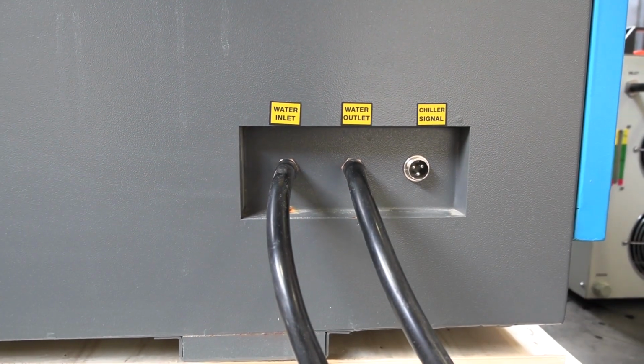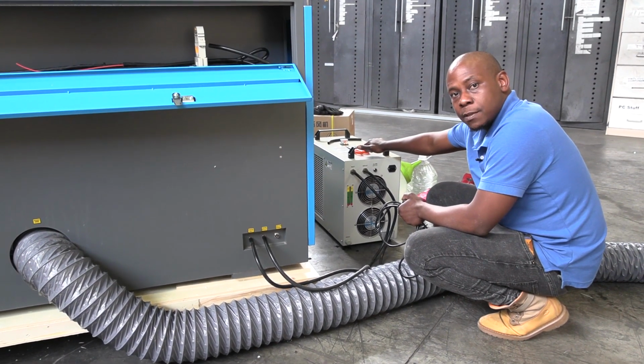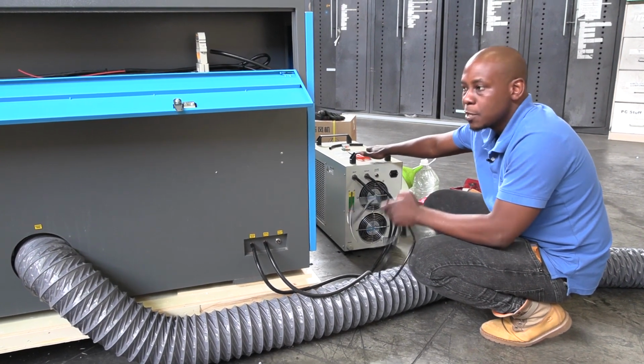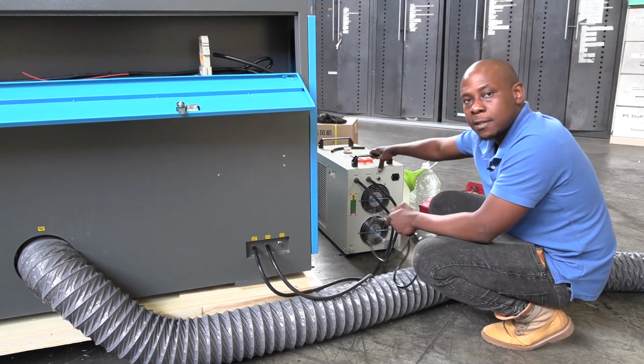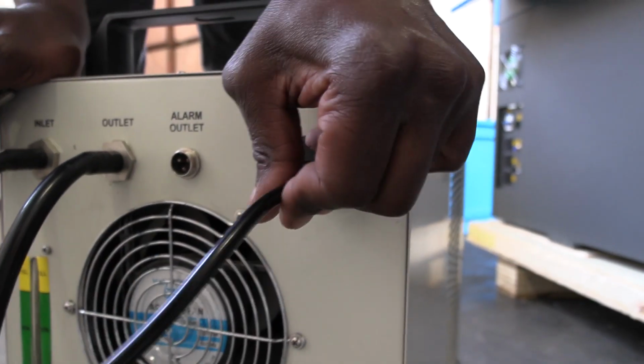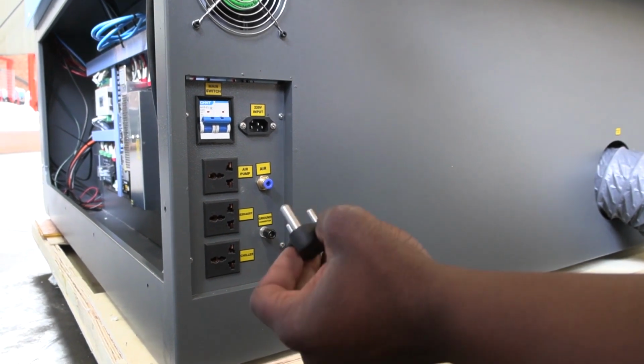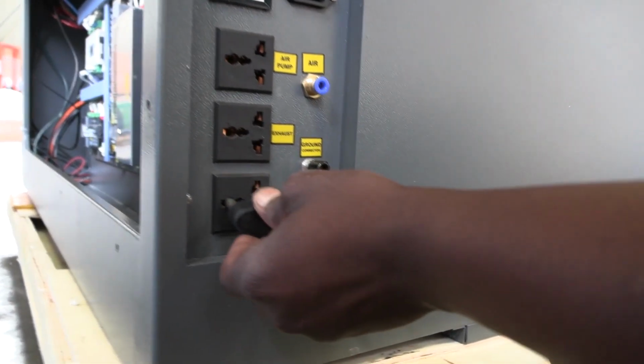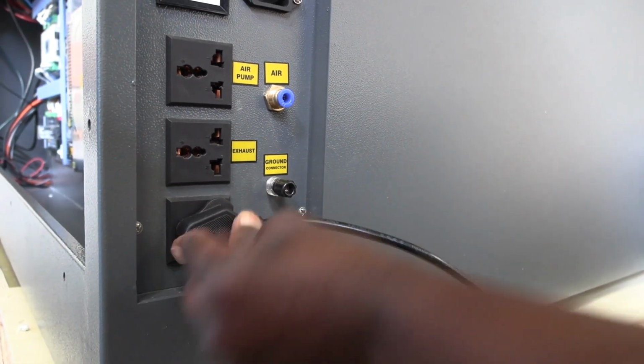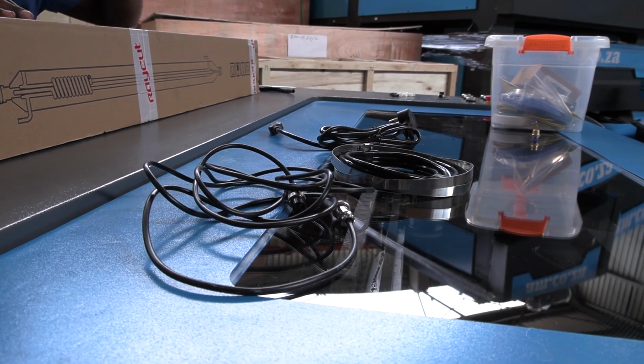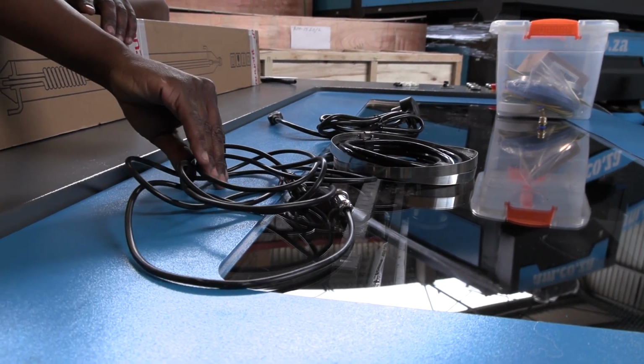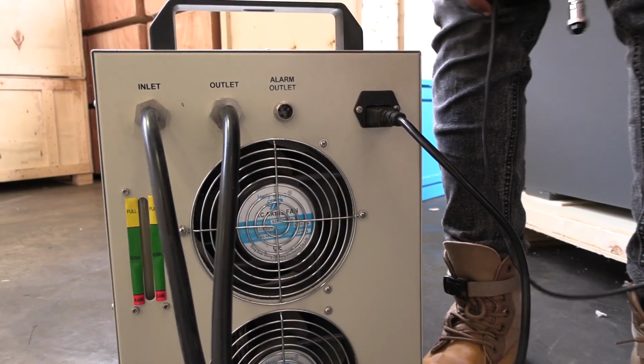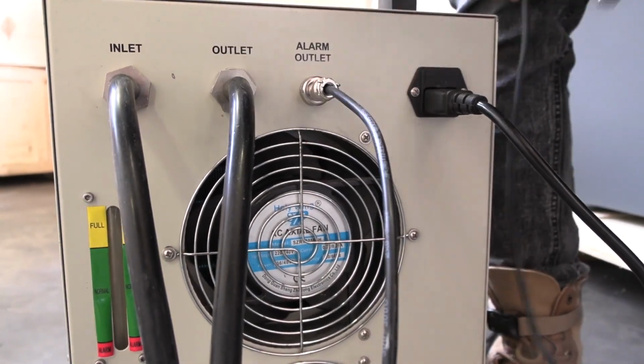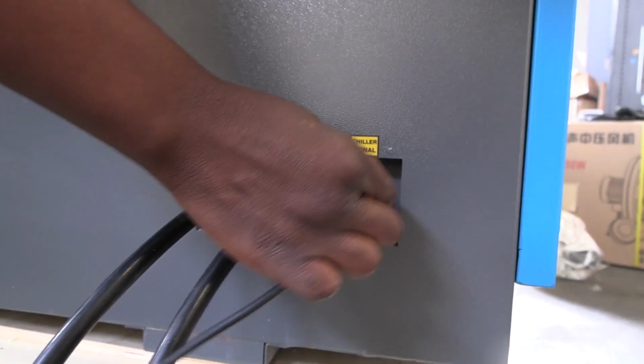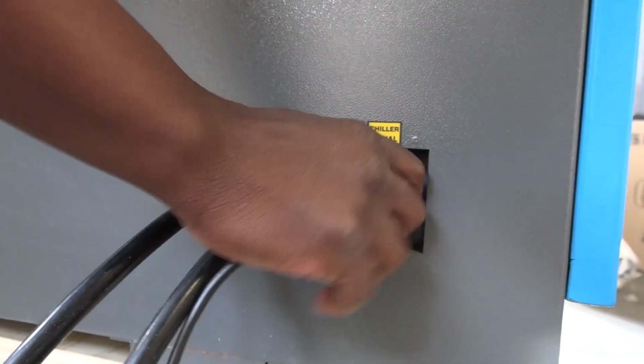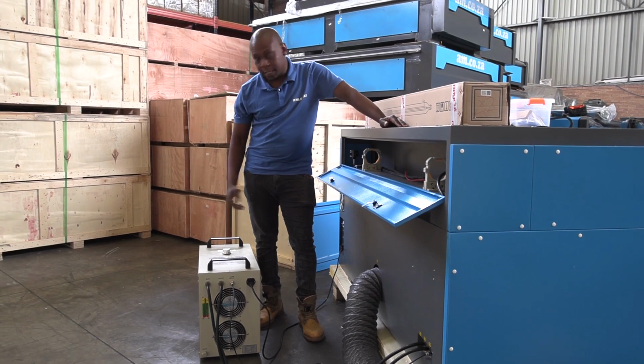So it's vice versa. Now I'm going to find a comfortable position to place my chiller behind the machine so I can also connect the power cable to the outlet onto the machine. Plugging in my power cable. Now I'm going to connect my chiller power cable onto the outlet socket labeled for the chiller. Alright, now all I have to do is connect my signal cable onto the machine and onto the chiller. Now the chiller is done.